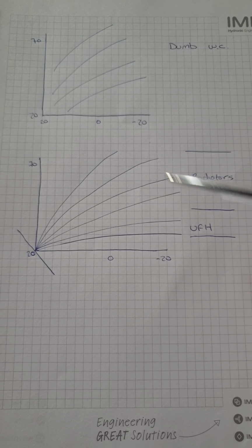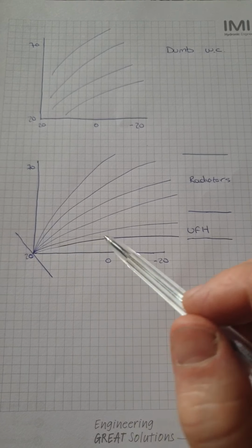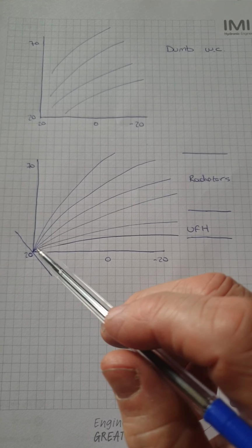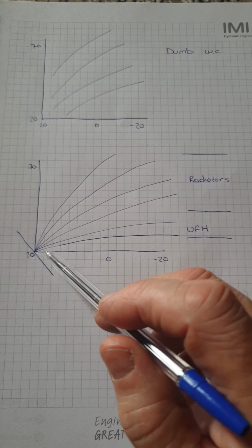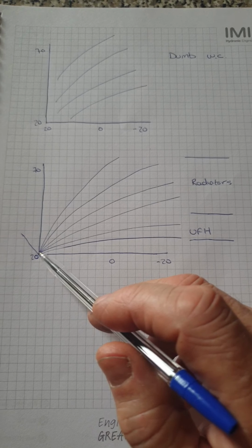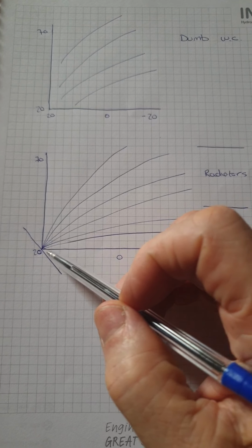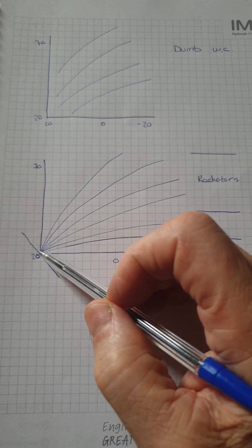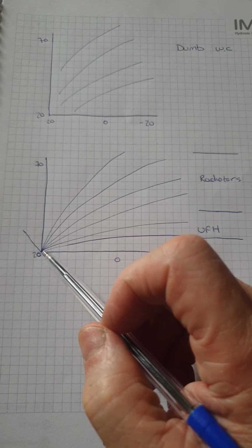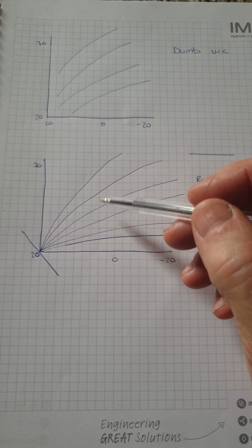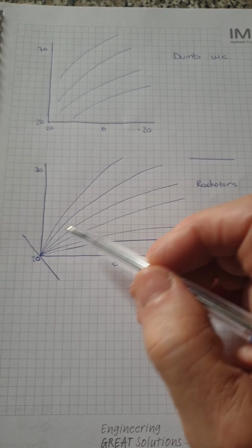Anyway, saying that, the Viessmann one seems to work perfectly well, and it has all these levels of control. So basically all the curves on the Viessmann weather comp amalgamate back at a start point, and this start point is usually a match between the flow temperature and the design room temperature. So this would be a flow temperature of 20 and a room temperature of 20, and kind of worked out that the DT at this point would be 0, and the reason it'd be 0 is pretty much it's turned off because there's no heat requirement. And what I believe happens is that at your main design function you'll have your delta T 20, but that delta T is going to drop back and narrow as we come back down this curve.